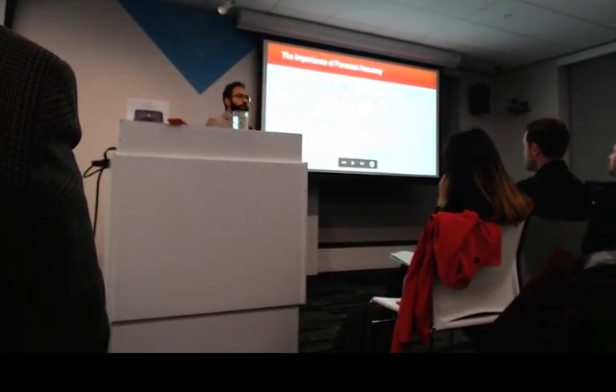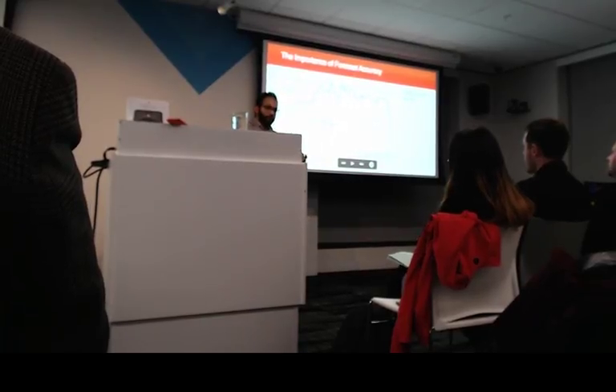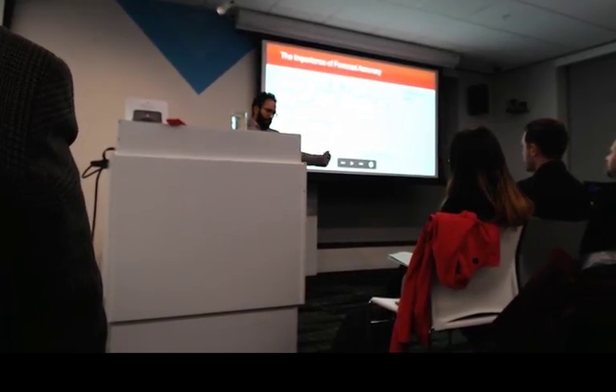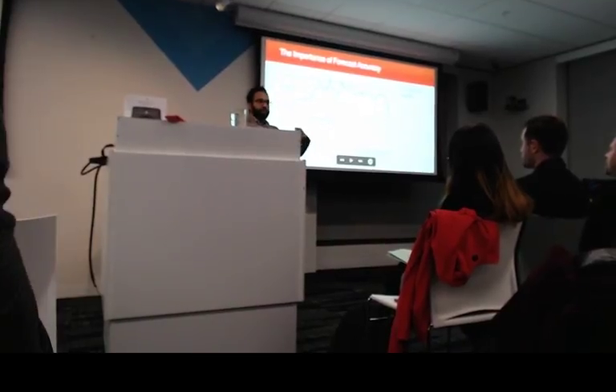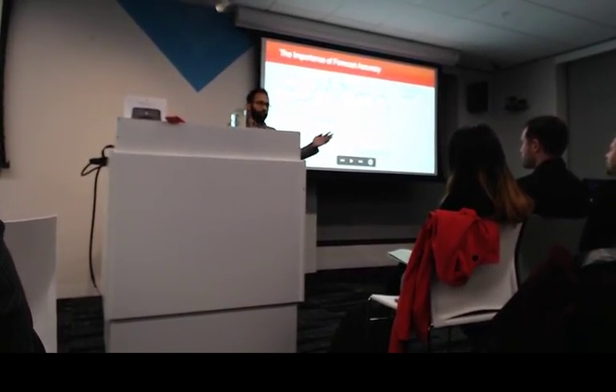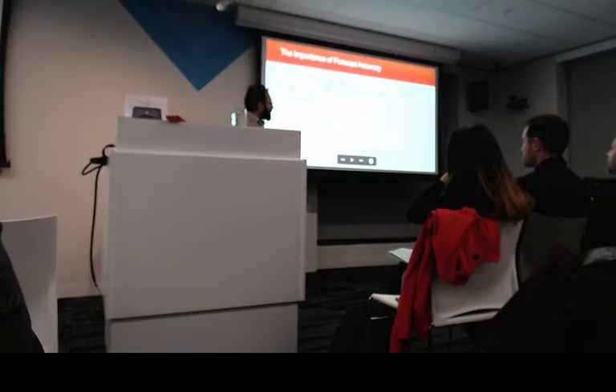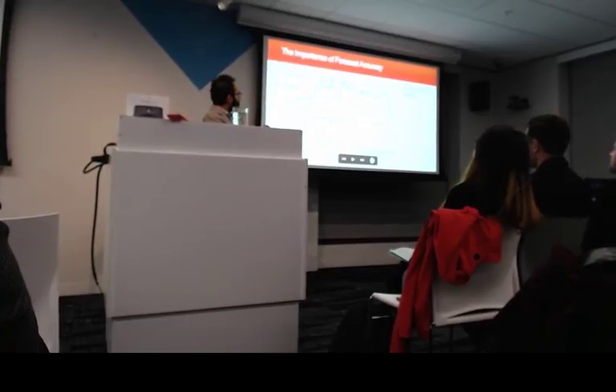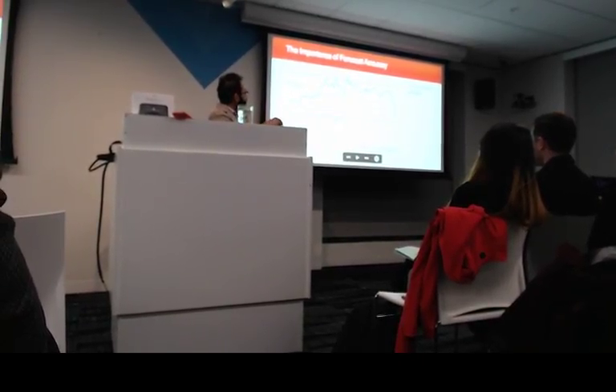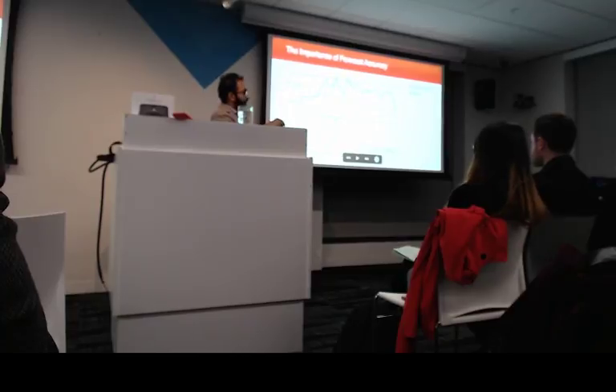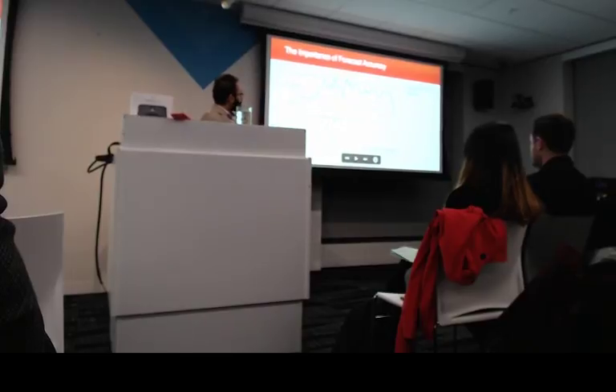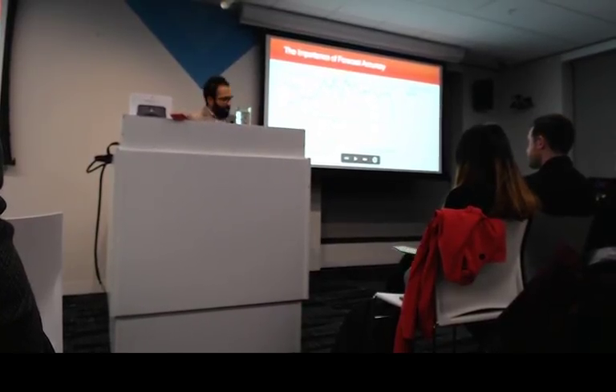Now we have these real-time algorithms that are running on the power monitor. So within the forecast intervals, they detect any changes, basically any difference between the actual load and your forecast, and they'll adjust accordingly. Because of those algorithms, you could still get 18. So when we simulate with this red set point, as we'll call it, on the black load, you would still get a full 18 kilowatt reduction. So you'd still save the customer money. But for every kilowatt reduced, you would have to use 2.39 kilowatt hours of energy to do that reduction.